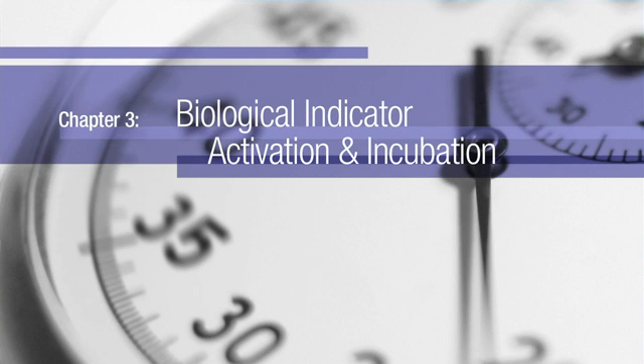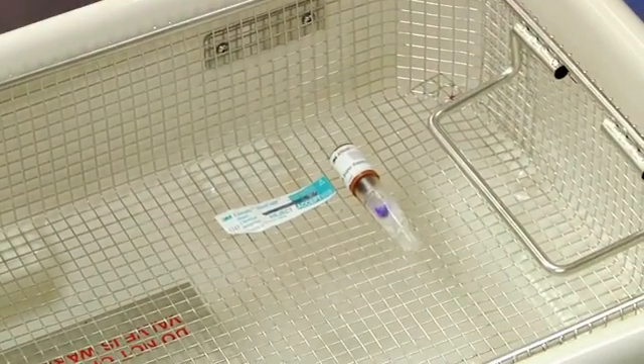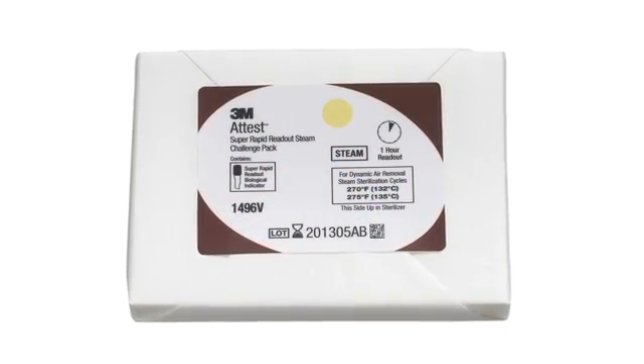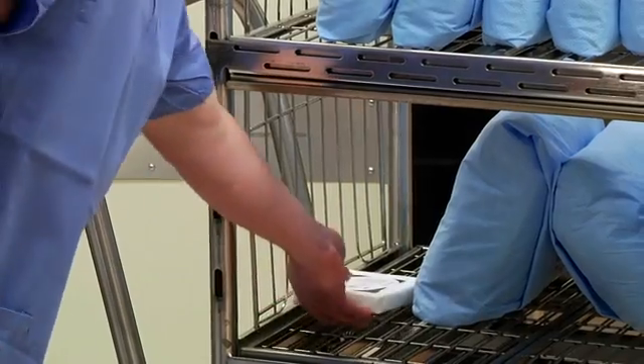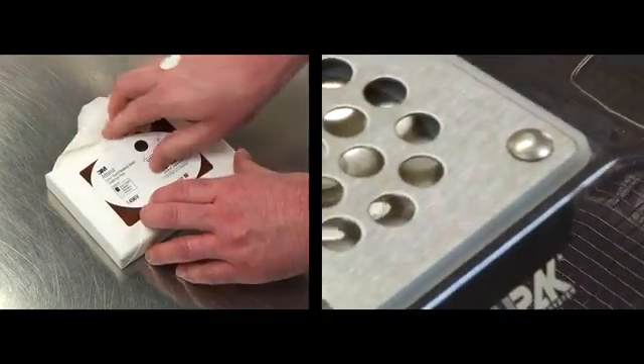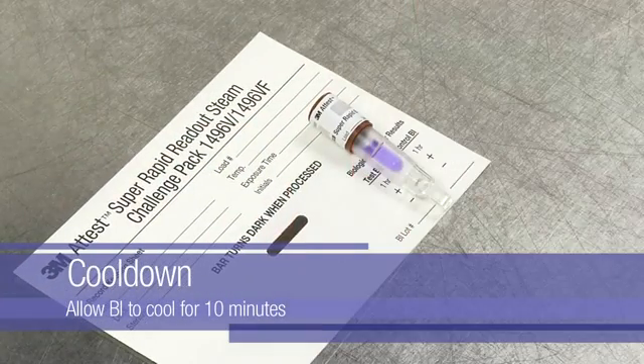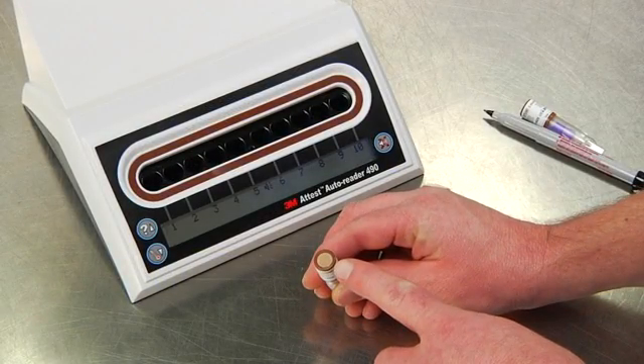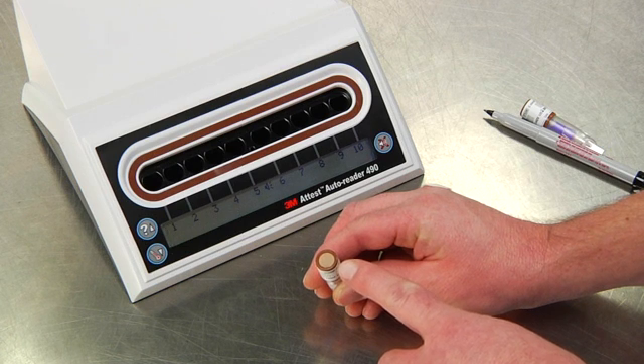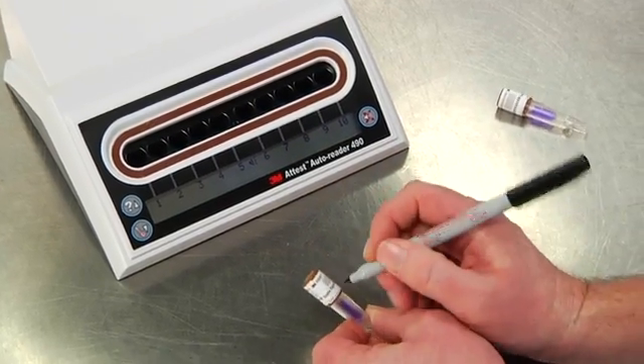Let's look at how to activate and incubate a SuperRapid BI in the Auto Reader 490. The first step is to remove the BI or Challenge Pack from the sterilizer. If using an Attest SuperRapid Readout BI Challenge Pack, scan the 2D barcode on the label to record product catalog number and lot code. Open the Challenge Pack and allow the Attest SuperRapid BI to cool for 10 minutes before activating. Check the process indicator on the cap of the BI — a color change from pink to light brown confirms that the BI has been exposed to the steam process. Be sure to label the BI with the sterilizer, load number, and date.